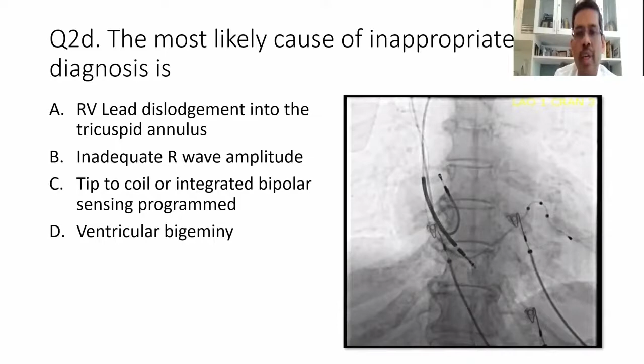Now, the episode here was detected in the VF zone, and hence the algorithm known as bigeminal avoidance is not applied. It is applicable in the VT zone, where it looks at these kinds of intervals in which one is a sinus or non-binned interval and the other is a tachycardia interval, and then avoids therapy by this algorithm called bigeminal avoidance. However, if these events are in the fibrillation zone, this algorithm does not work.